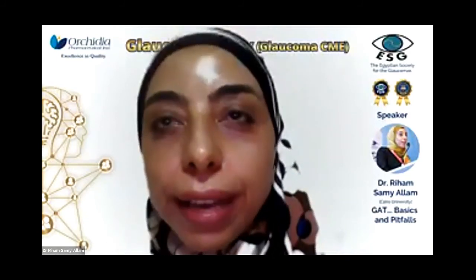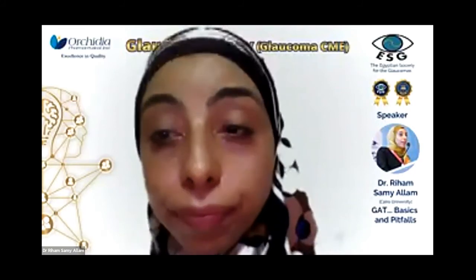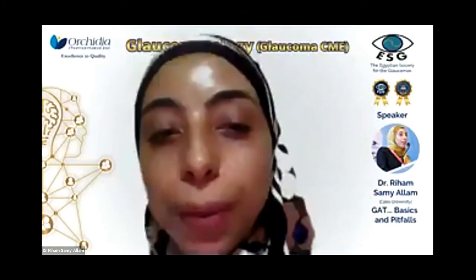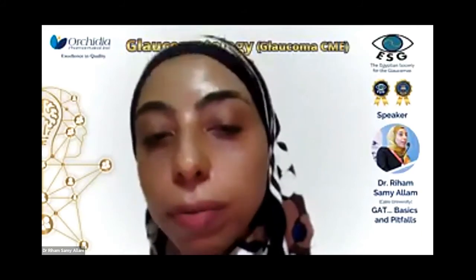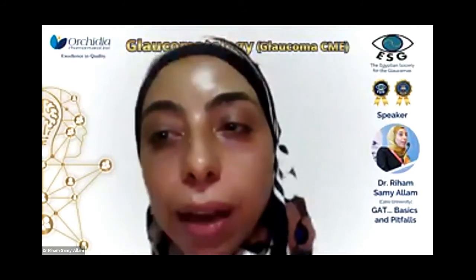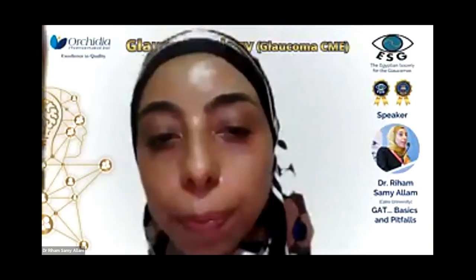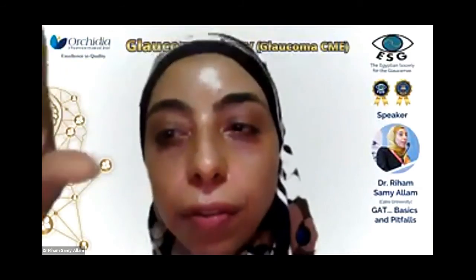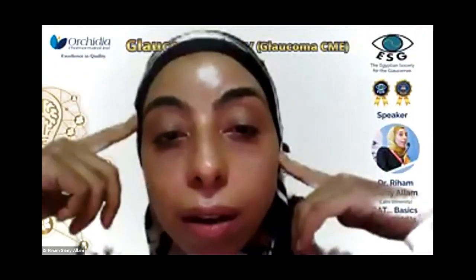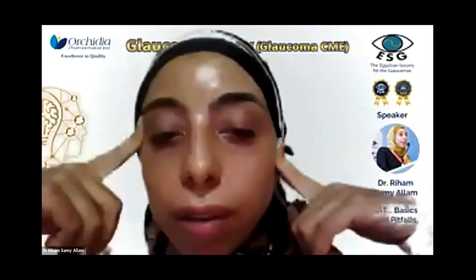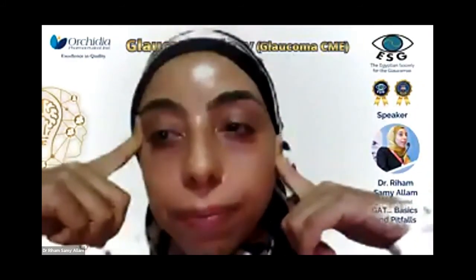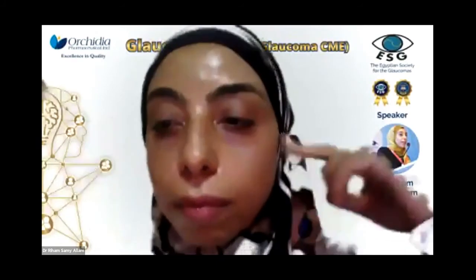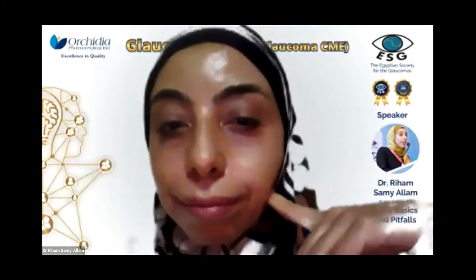I usually take a baseline Ora exam for the patient, and I usually phase these patients to pick the moment of the intraocular pressure peak. When I take a single reading for the corneal compensated pressure, I can tell arbitrarily the difference between it and my Goldmann. And then I repeat the Ora semi-annually in the first year and then annually later on. But this is not evidence-based, this is a personal practice. So refractive surgery still remains an issue with measuring intraocular pressure.